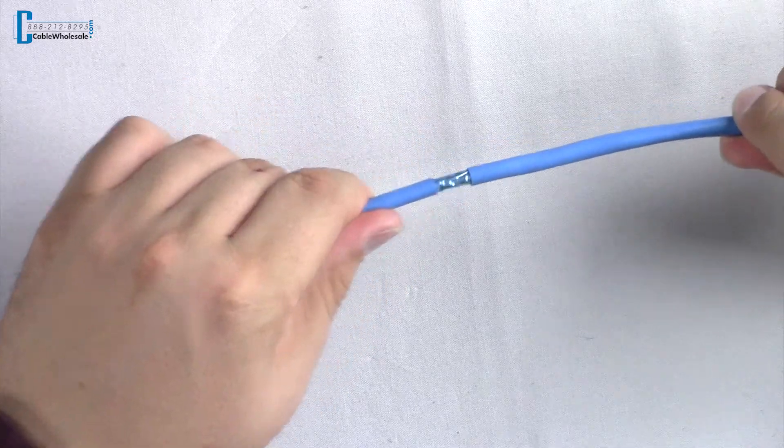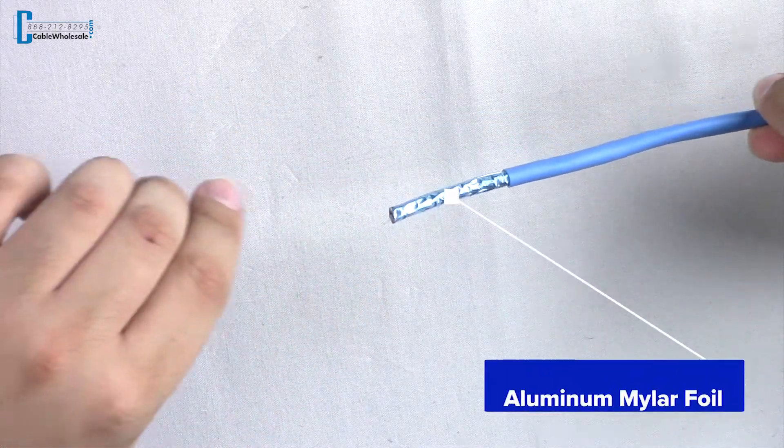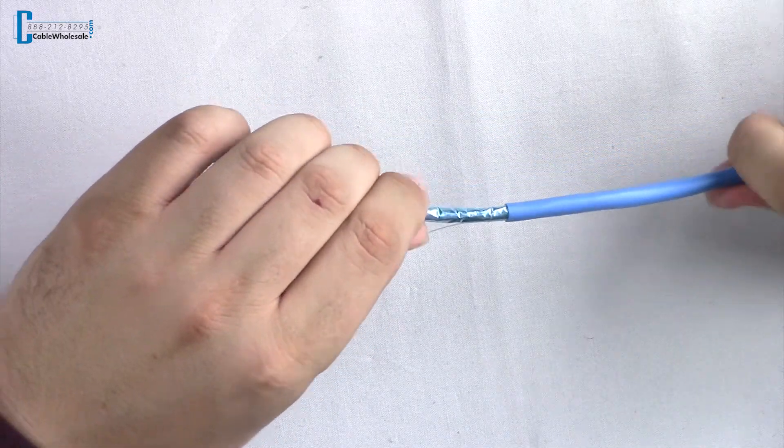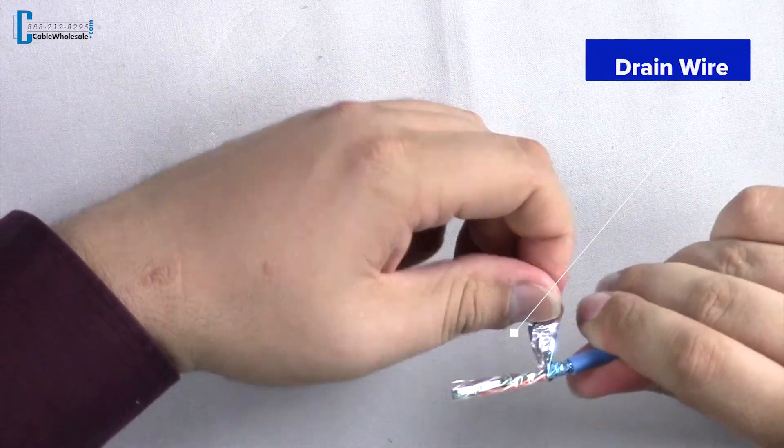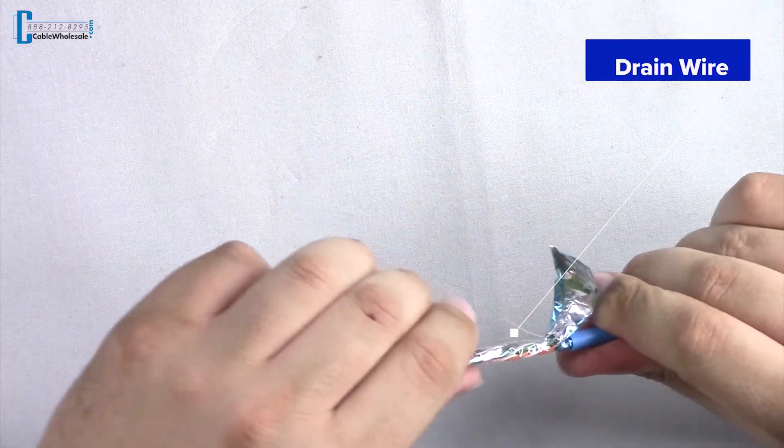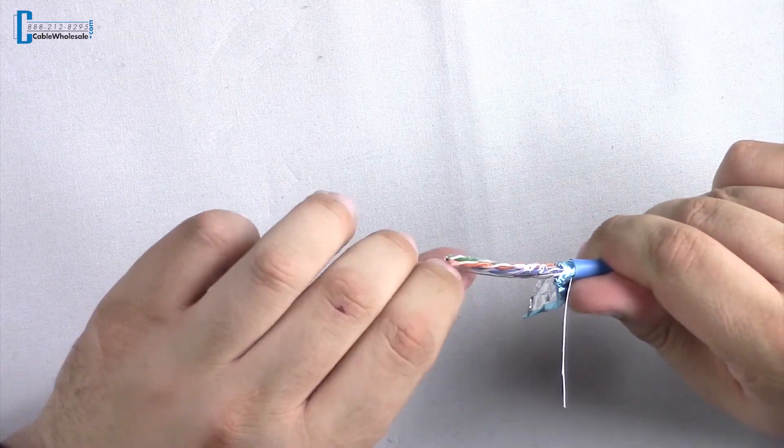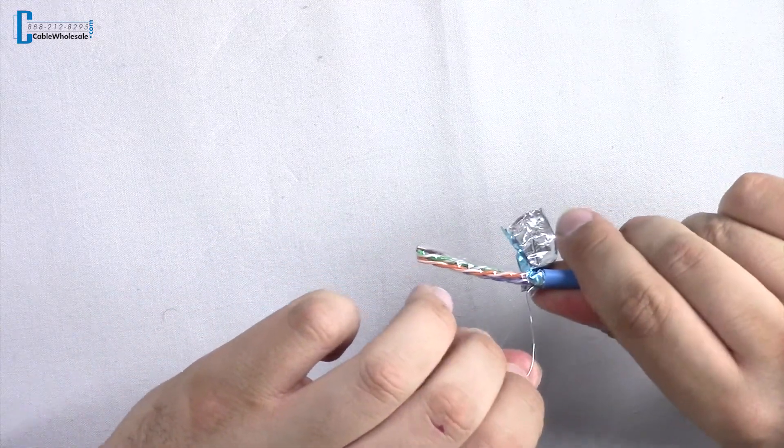Well Rick, FTP shielded ethernet cables feature an aluminum mylar foil shield under the outer jacket that surrounds all four pairs. It also has a drain wire that must be grounded to drain off the currents created by electromagnetic interference and radio frequency interference, EMI and RFI respectively.